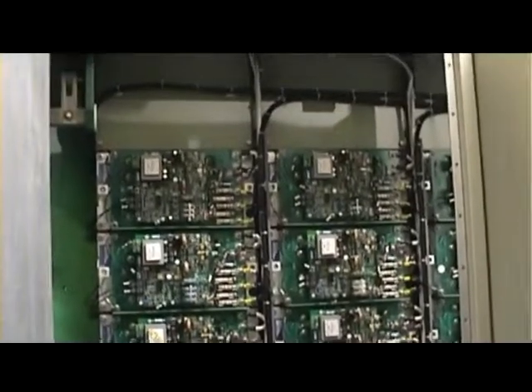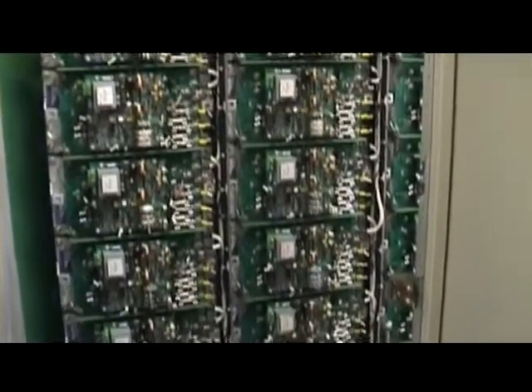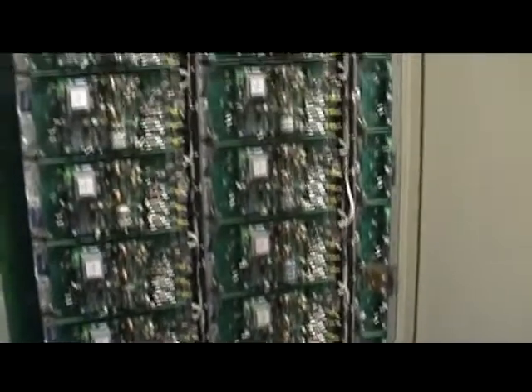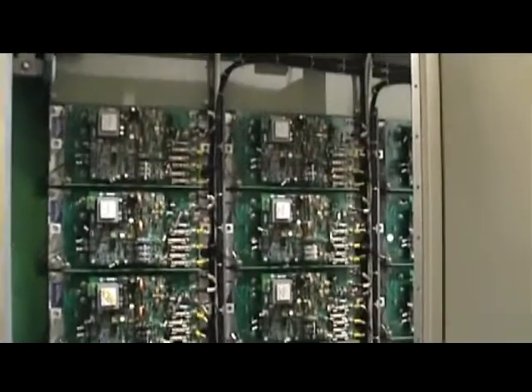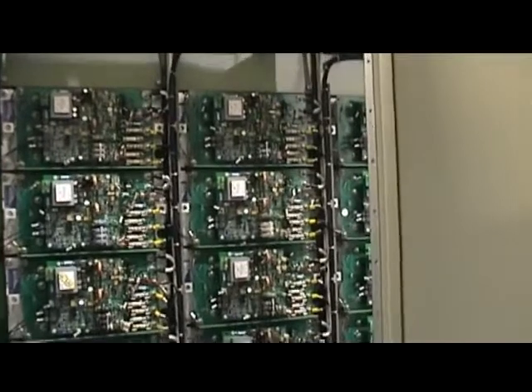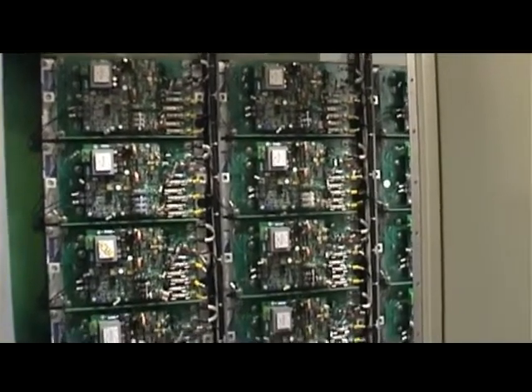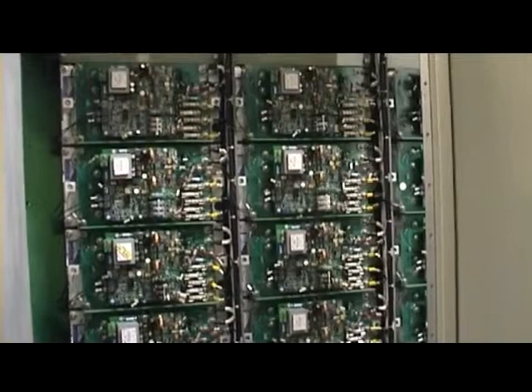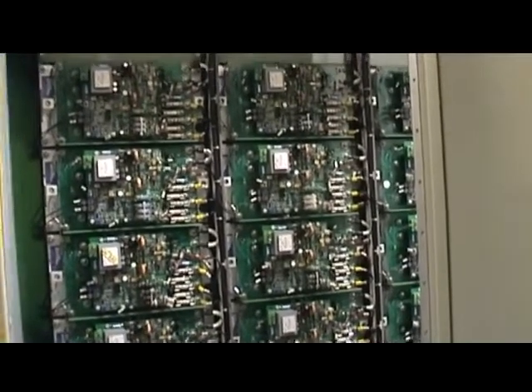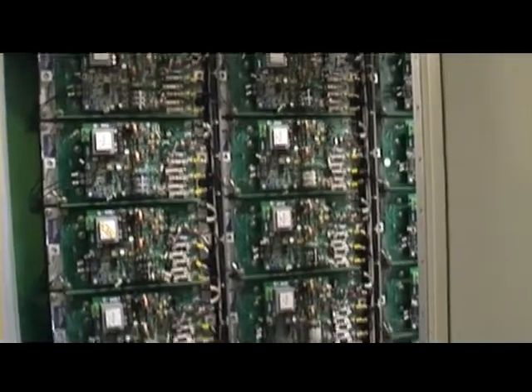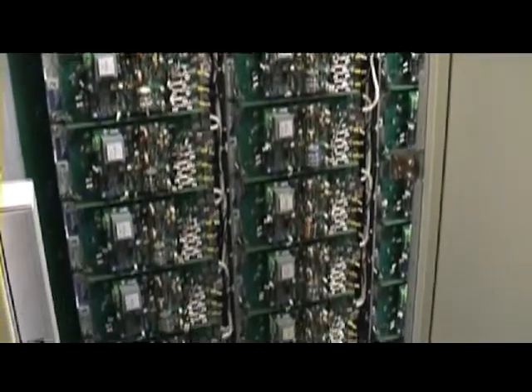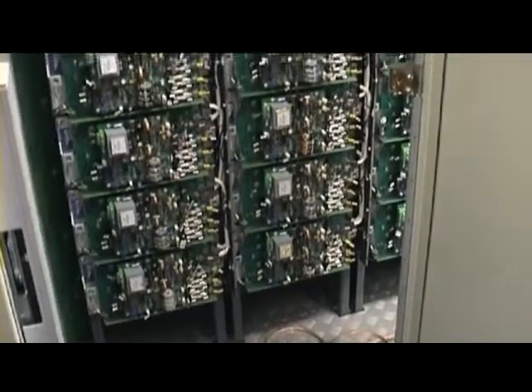The rear of the modules. Here are the front of the modules. There's 48 modules for high power and a couple of coarse steps. About 800 volts on each step. The digital system will let you switch as many modules on at an instant or as many as you don't want on at an instant to get the actual value of DC that you want at that point.